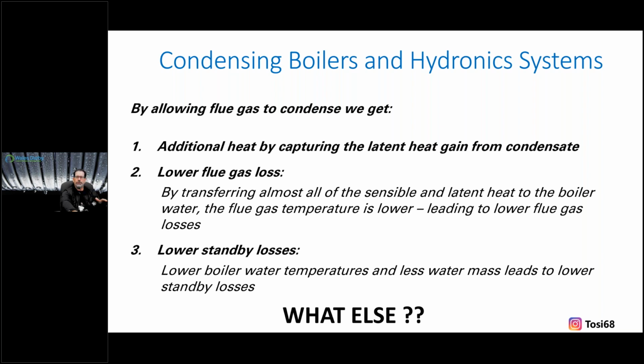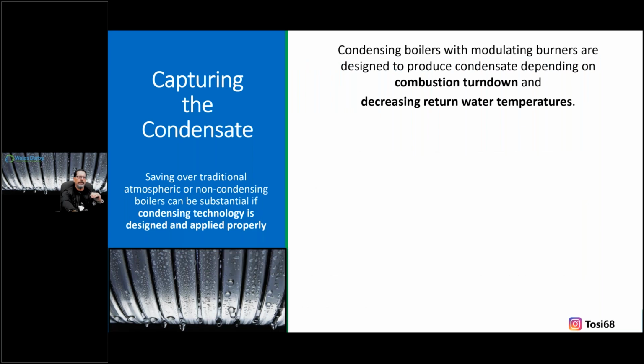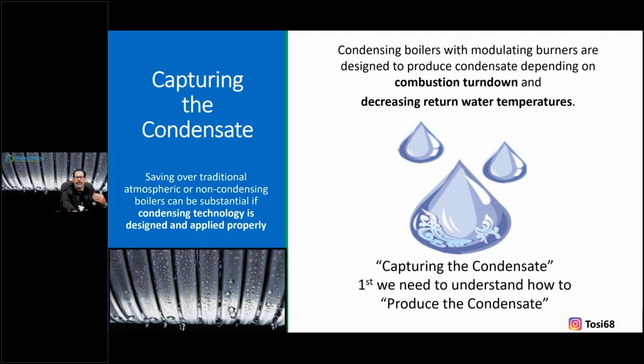So here, just in a natural gas or LP fired combustion, lowering water temperature has so many benefits for us to take advantage of. And this is what it really comes down to. Because of that high heat against cooler returning water, we have the ability to reclaim, right? Collapsing condensation. In the photo there, that's a heat exchanger, and you see the droplets, and that's what we jokingly say, making it rain. I want these flue gases not to have the opportunity to leave the building. We want them to be as cool as possible and continue to cool so that our vapor turns back into a liquid. In our venting, it's now pointing and coming back to our appliance, our heat engine, our boiler. And now these products of flue, again, vapor to a liquid, is now washing over and releasing more heat energy into our water, which we want to take advantage of.